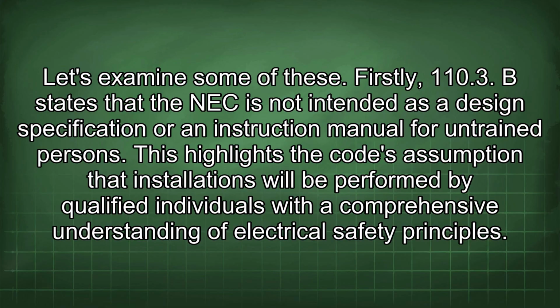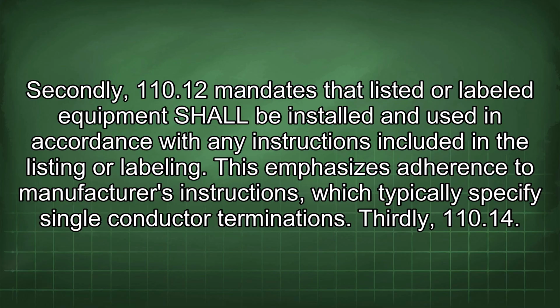Firstly, 110.3. This states that the NEC is not intended as a design specification or an instruction manual for untrained persons. This highlights the Code's assumption that installations will be performed by qualified individuals with a comprehensive understanding of electrical safety principles. Secondly, 110.12 mandates that listed or labeled equipment shall be installed and used in accordance with any instructions included in the listing or labeling. This emphasizes adherence to manufacturer's instructions, which typically specify single conductor terminations.